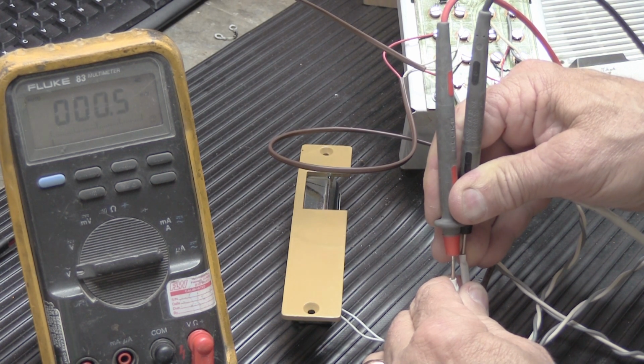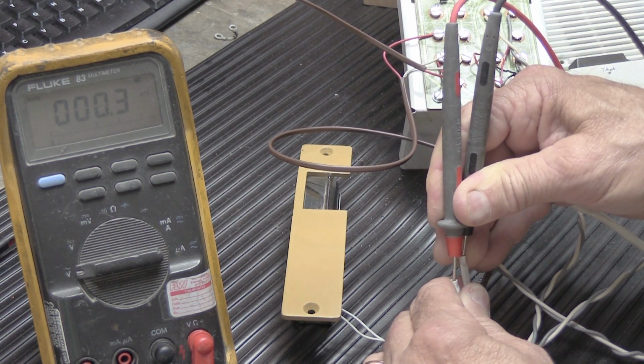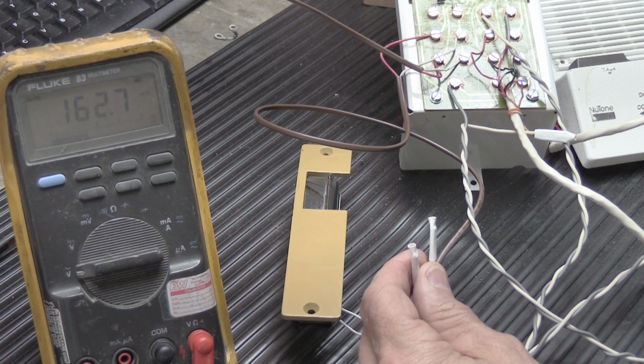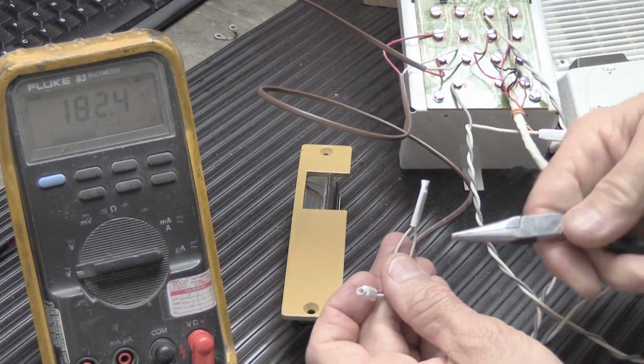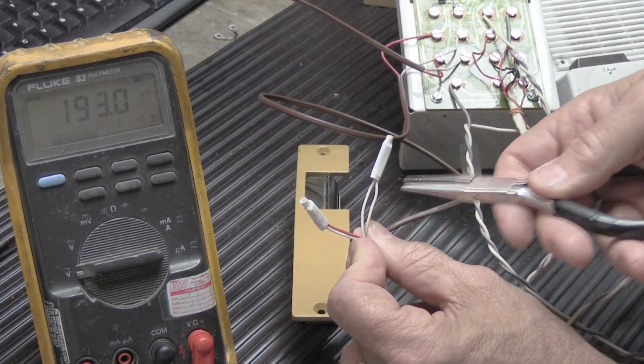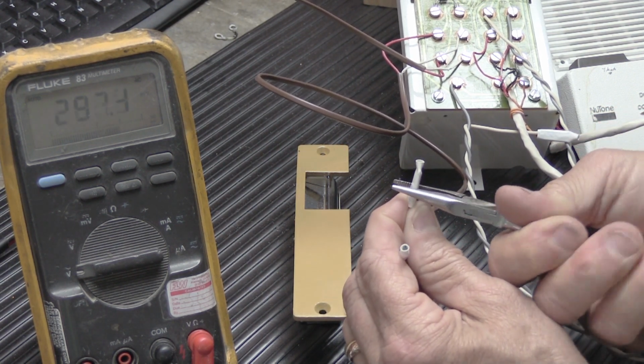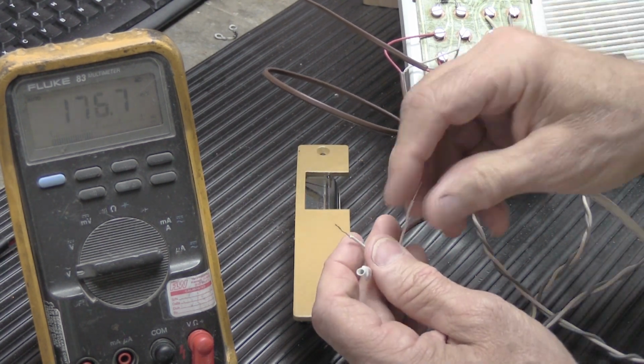before we disconnect it. And again, sort of like what we had on our 478 control amplifier, we have 0.3 millivolt. It's almost nothing. Once you've done that, now what we're going to do is disconnect, or unsplice, one of the 2 wires that connect from the 478 to the wires on the door release. This particular installation happens to have these little crimp connectors, and if I squeeze it carefully, I can open it up and disconnect the 2 wires.